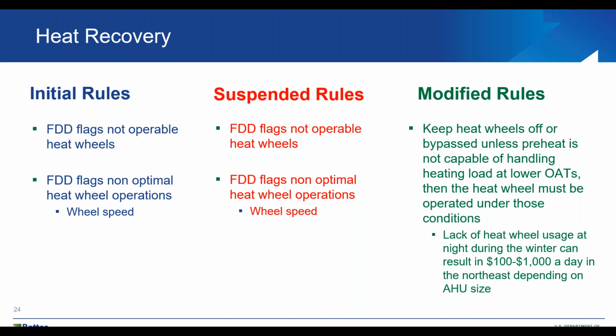There are two different types of rules in how to operate the heat recovery system. In normal cases, we'd want to shut it off under COVID, so there's no contamination, suspend the rules. So it would flip around. So you'd want to make sure it flags when it's operating, because you don't want it to operate anymore. However, you also need to modify it, because under low outside air temperature conditions, the heating system may not have been sized large enough initially to handle the full load. So you may need to operate it under very cold conditions, regardless of COVID or not, because you don't want a freezing building. So that would have the overriding factor, and the rule needs to be modified to indicate that the temperature is getting too cold in there.